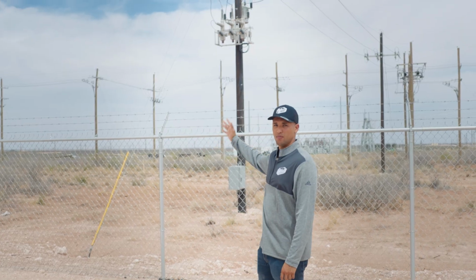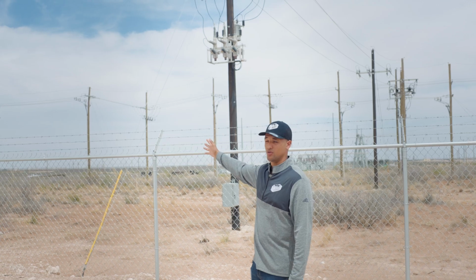On this offtake pole behind me, you can see our site recloser. Another way to look at a recloser is as a big surge protector. It monitors all the voltages coming into the site, and if anything gets unstable or there are power surges, it physically disconnects the power flowing to the site to keep our infrastructure and ASICs protected.